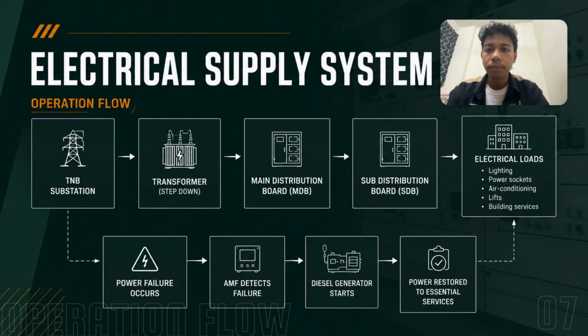Next, this slide shows the operation flow of the electrical supply system. During normal operation, electricity is supplied from a TNB substation and passes through a transformer, where the voltage is stepped down to a suitable level. The electricity is then distributed to the main distribution board, followed by the sub-distribution board, before supplying electrical loads such as lighting, power sockets, air conditioning, lifts, and other building services.